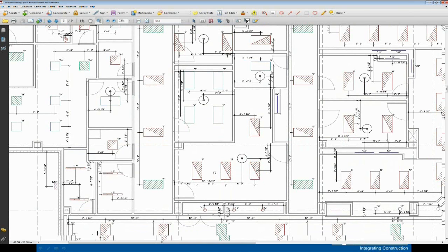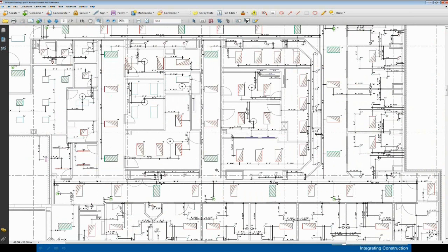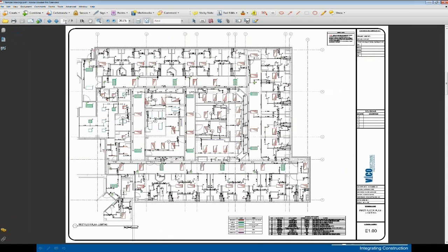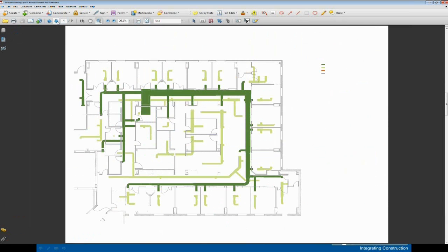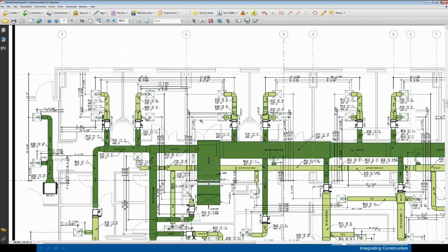So before a drawing like this gets done, during really one of the earliest steps in our coordination process, making sure that the HVAC diffusers and grills align with the lights, align with the sprinkler heads, and that the reflected ceiling plans are going to come out nice and even on site. So that's another really good benefit to the service that we provide, is that we can go to the level of detail of coordinating the reflected ceiling plan.